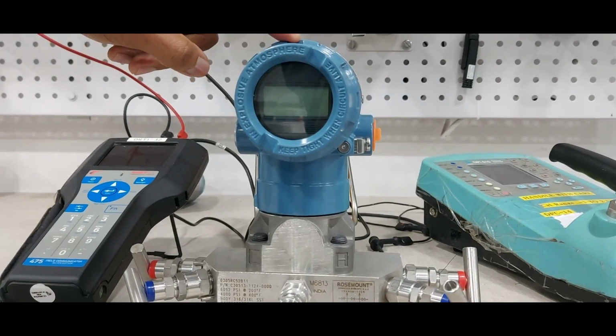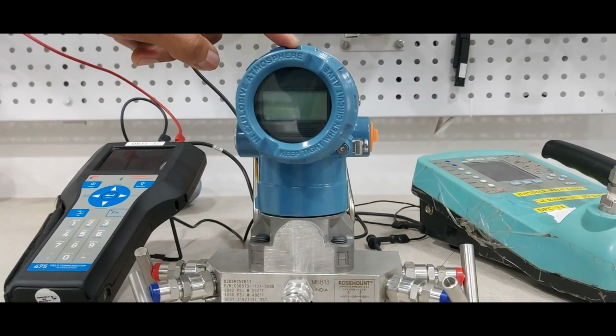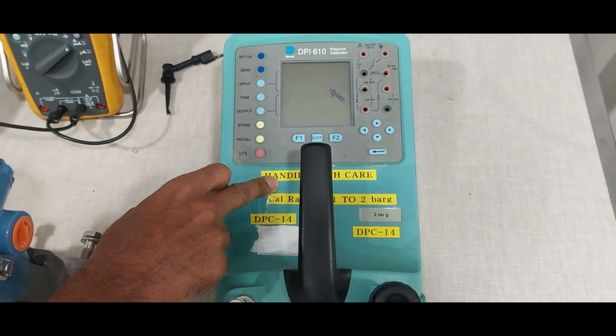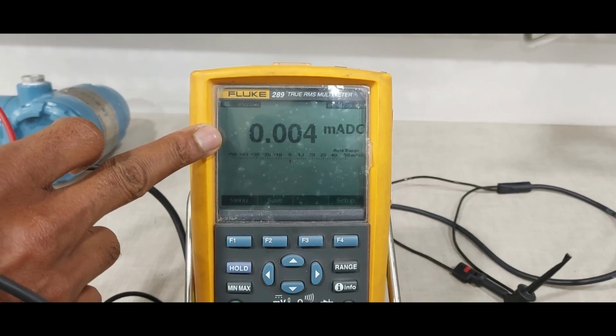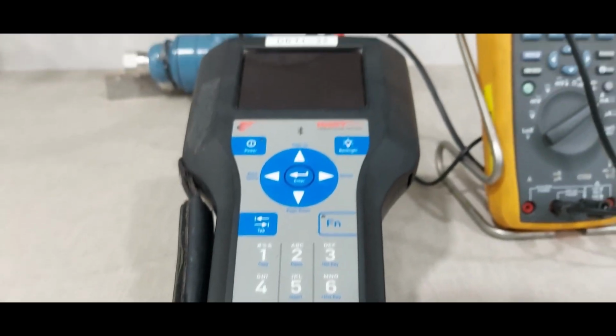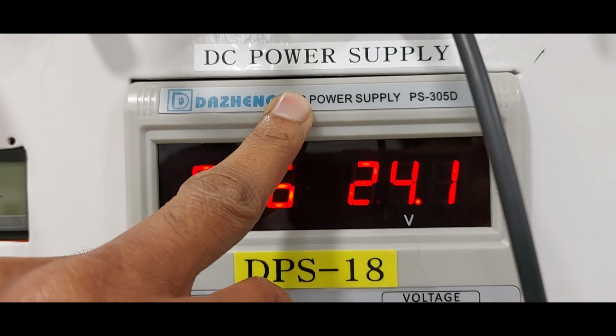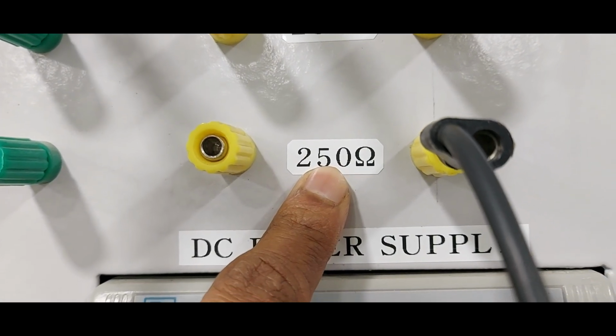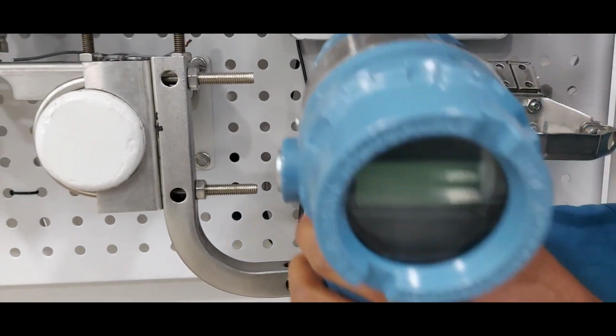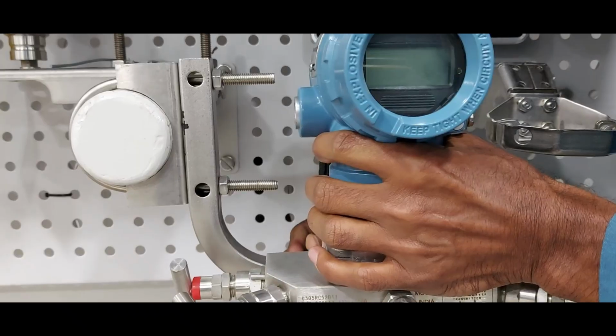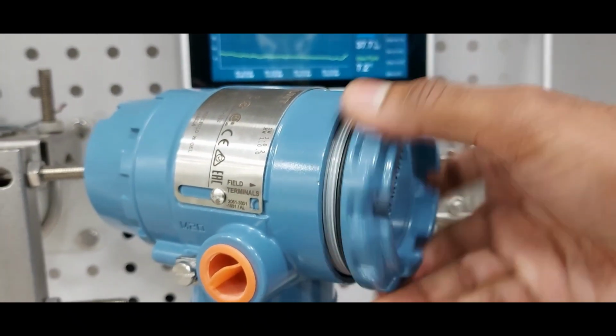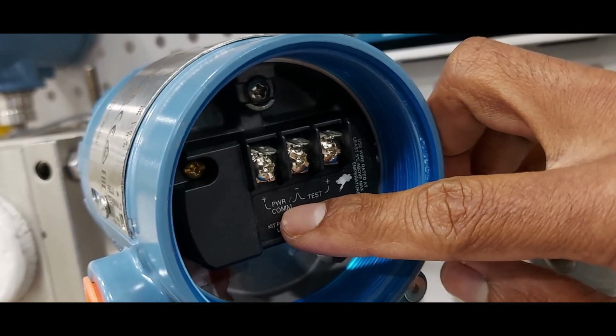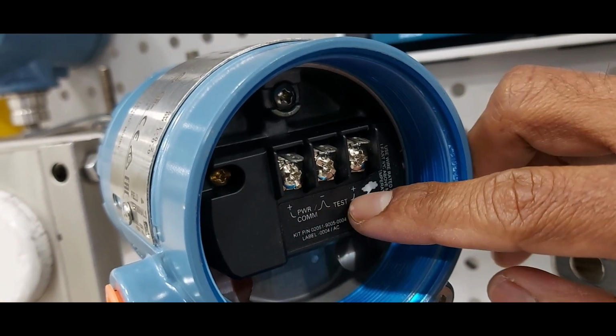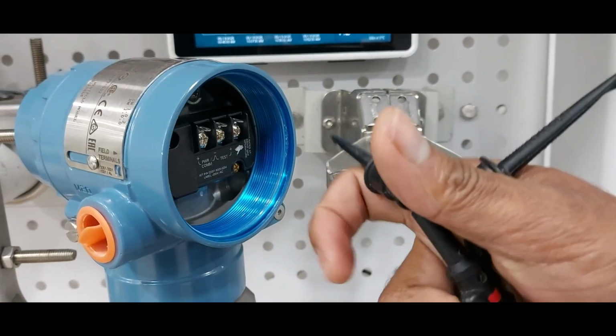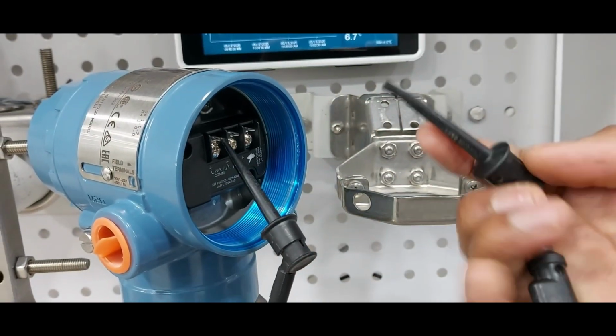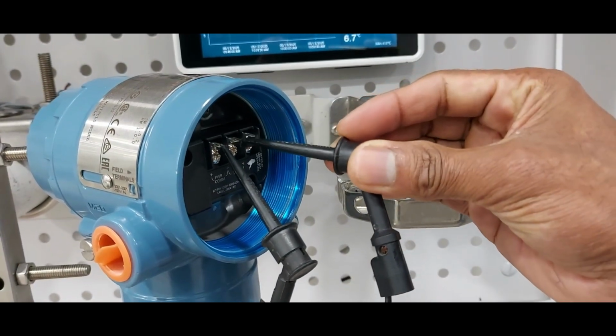DP type flow transmitter calibration, minimum required equipment: one pneumatic pressure calibrator low range, reference multimeter, field communicator, 24 volt power supply, 250 ohm resistor. Next, on the transmitter, insert the clamp, remove the back cover, power supply terminal, positive, negative and test terminal. Positive line connected to transmitter positive terminal, negative line connected to transmitter negative terminal.